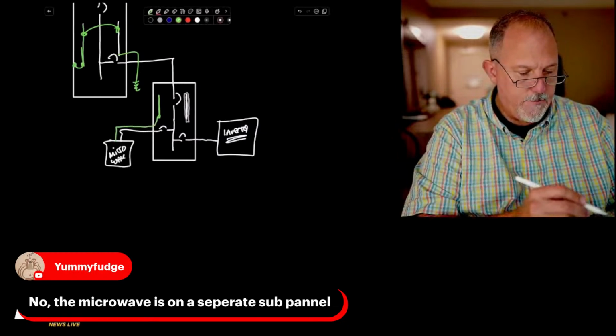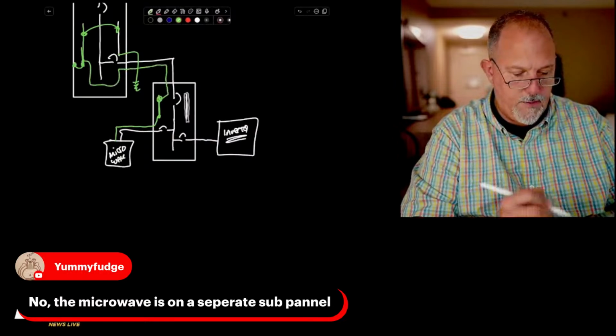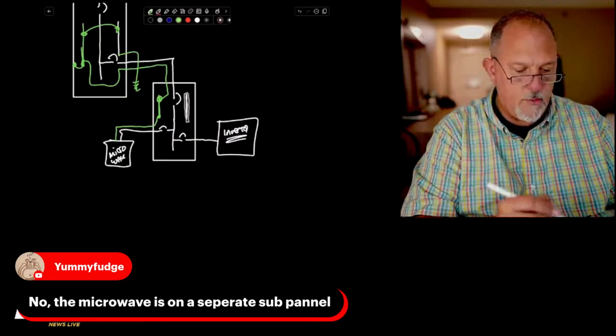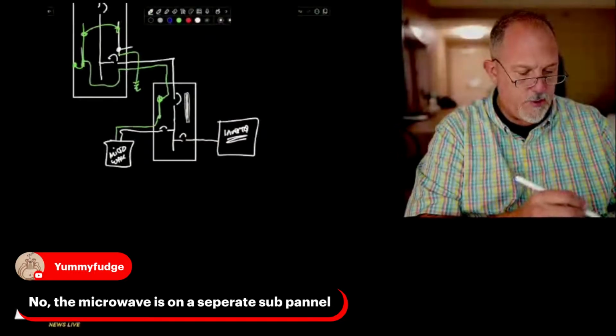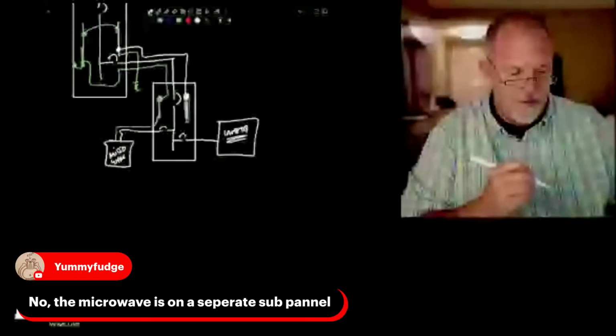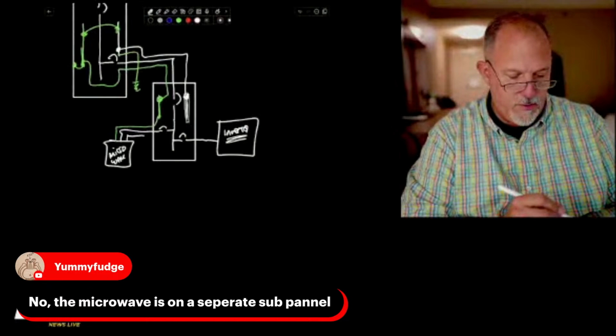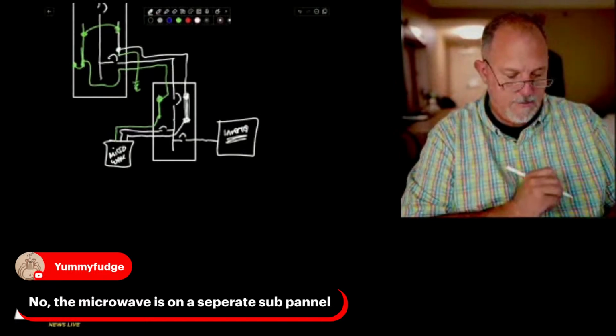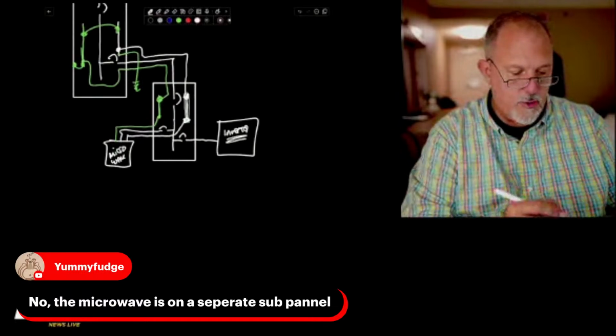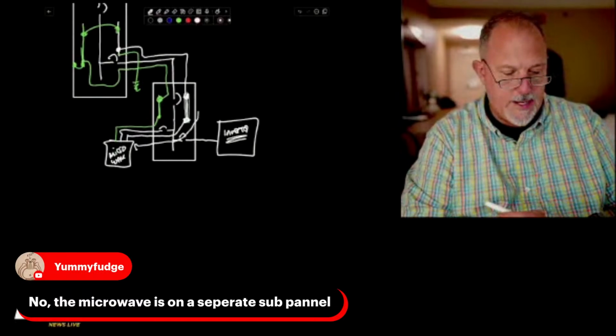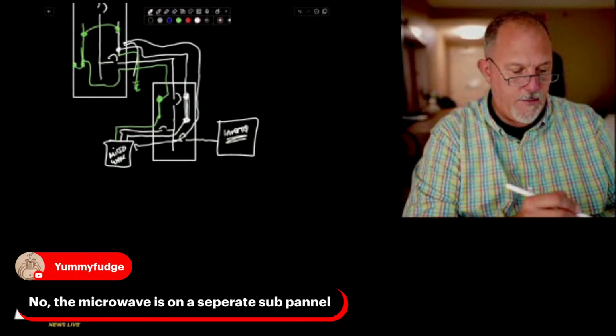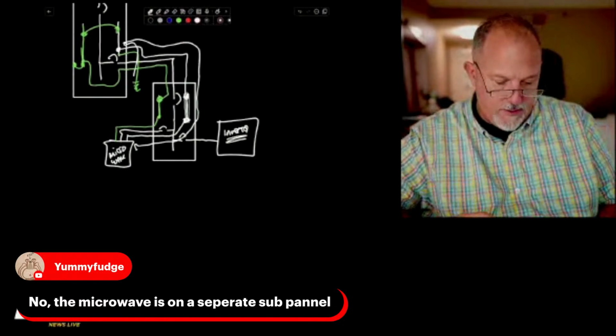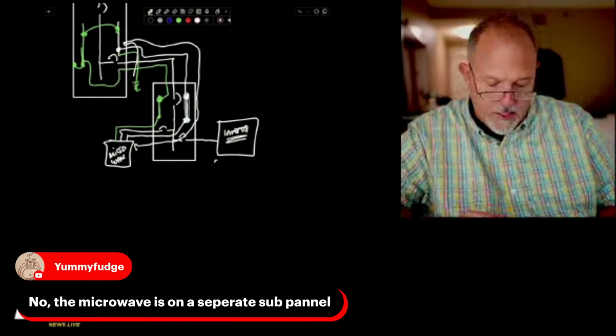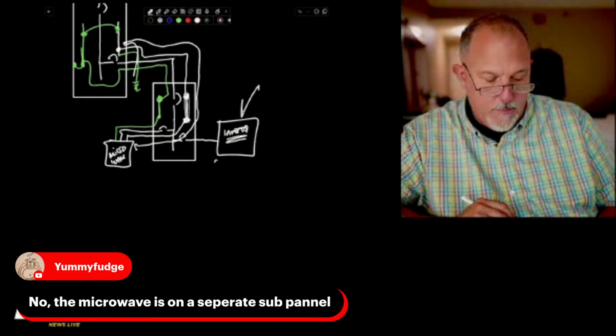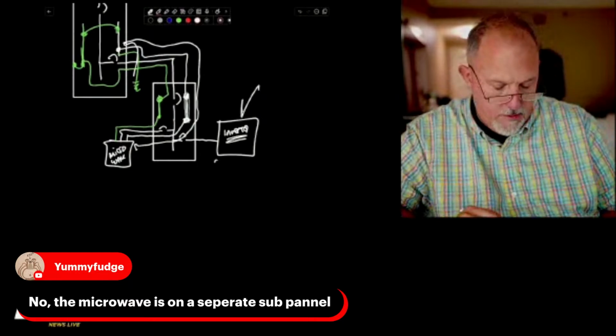It grounds there, and I would come off of here, and I would go with this, and I would come with a neutral, right? I would pull my neutral and land there, and then I come off of here with my neutral. I land it to there. So my neutral current still flows back up through here, back up through there, and then back down to ground. So I still have a ground reference. Now, it's not going back to the neutral. It's not going back to the inverter. But I have a return path.